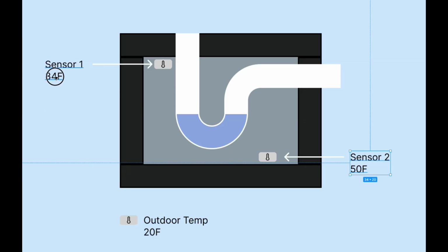However, we also noticed that the sensor up here near the top of the box was reading 34 degrees Fahrenheit at the same time as this was reading 50 and this was reading 20. 34 is pretty close to freezing, so that's something that we wanted to address. And I think what might have been happening was that there's a draft coming in from the top here where the pipe meets the box. It might have not been perfectly sealed up. And so there was a little bit of draft coming in and affecting that sensor and making it quite a bit colder than it otherwise would be.